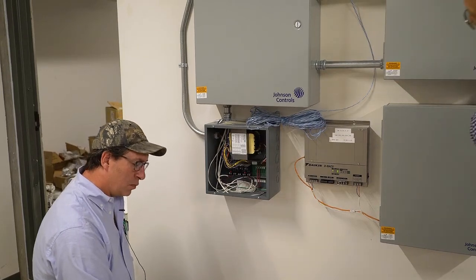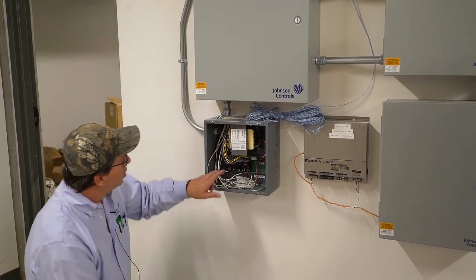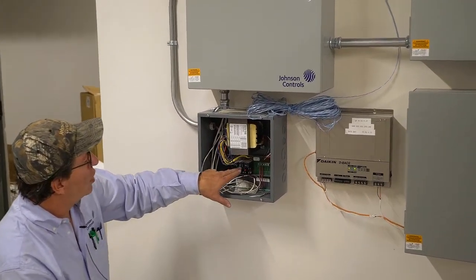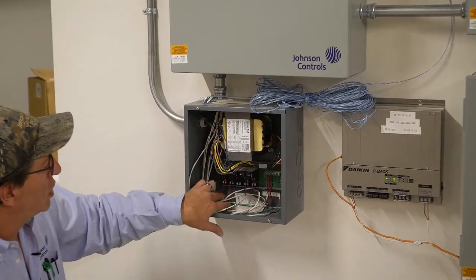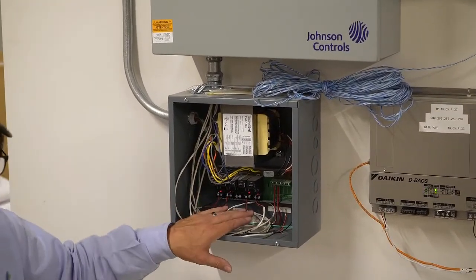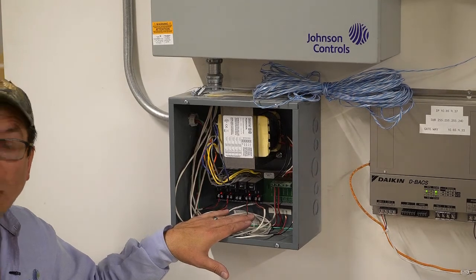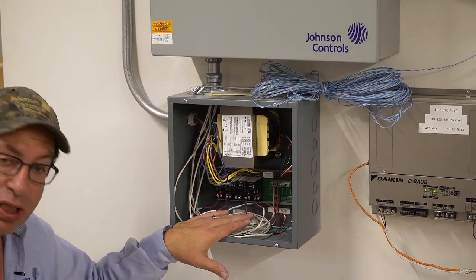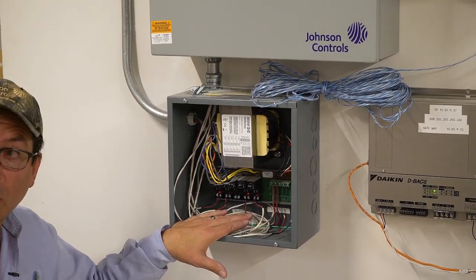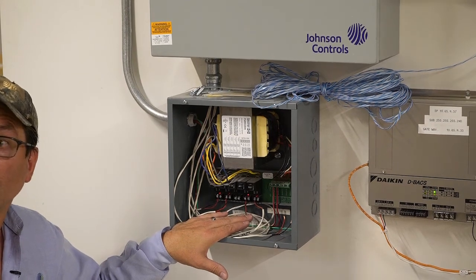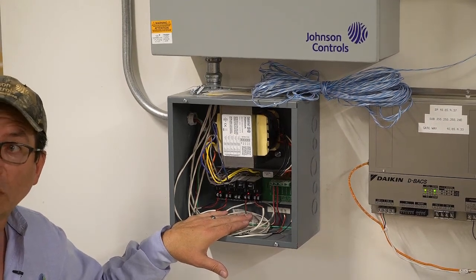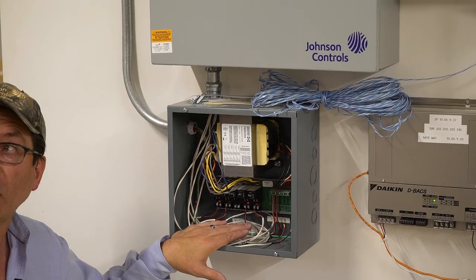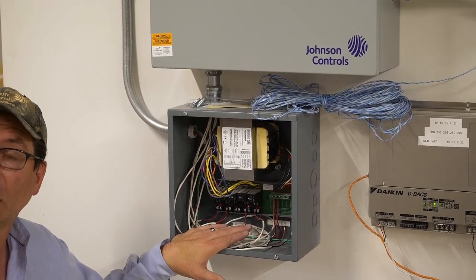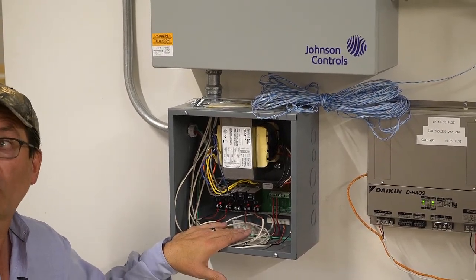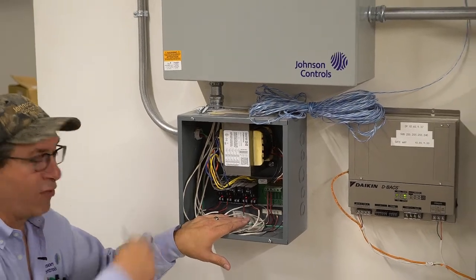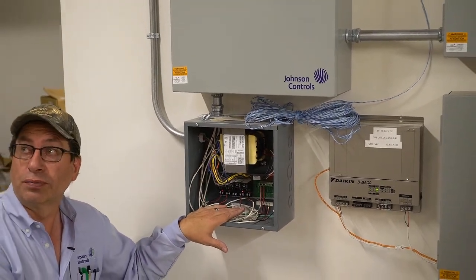500 amp transformer. It's broken out into 5 100 amps. So we use this for our 24-volt power going to the TEC controllers and any remote FEC controllers. Like all those TECs going for the H1 through H8 through that radiant heat, those all require 24 volts. So we try to put an average of 5 of them on the circuit.